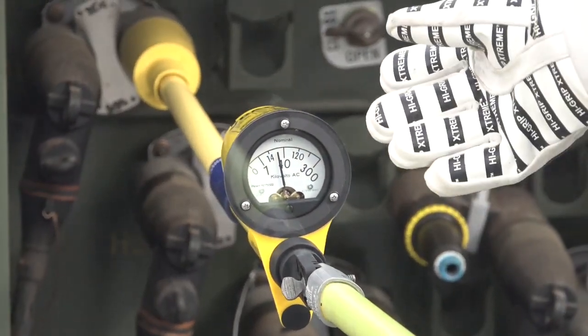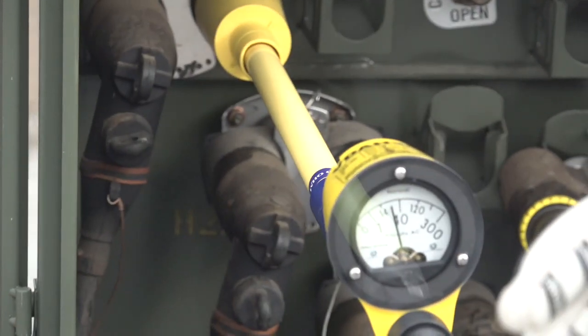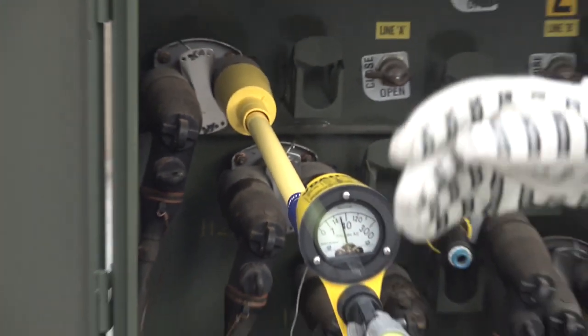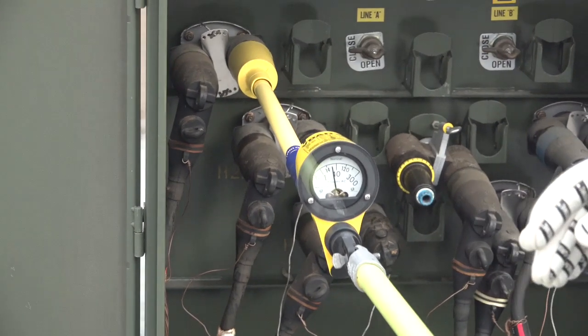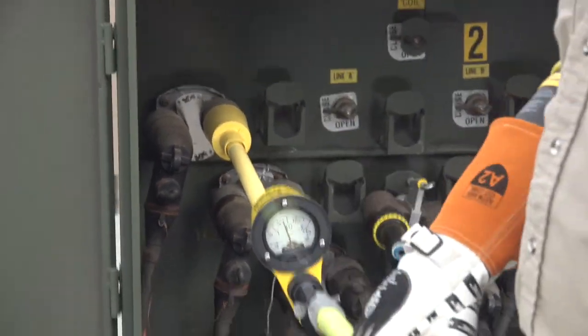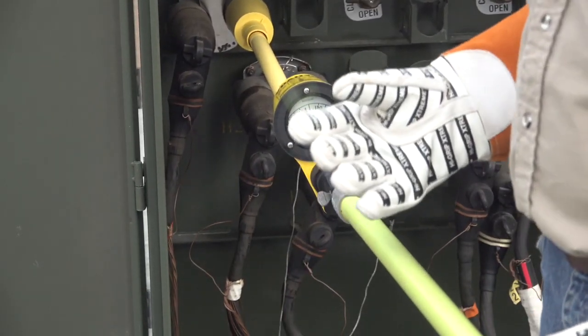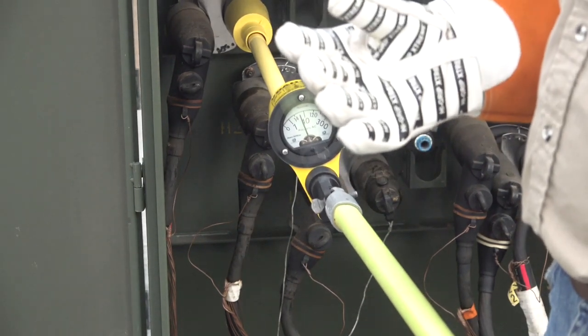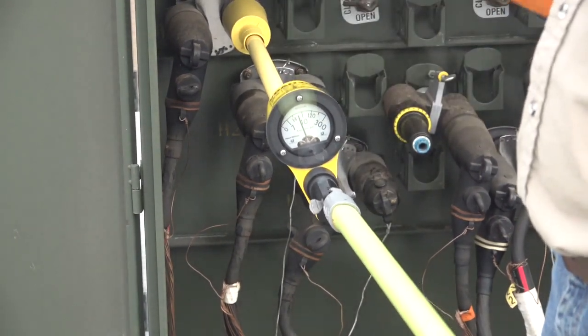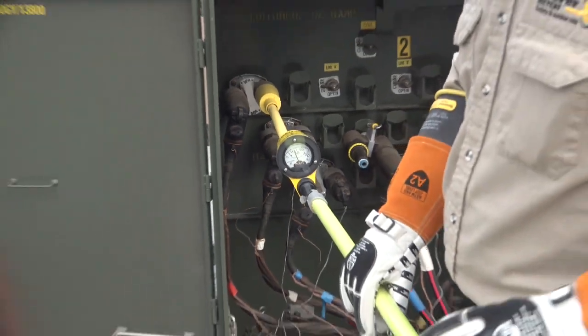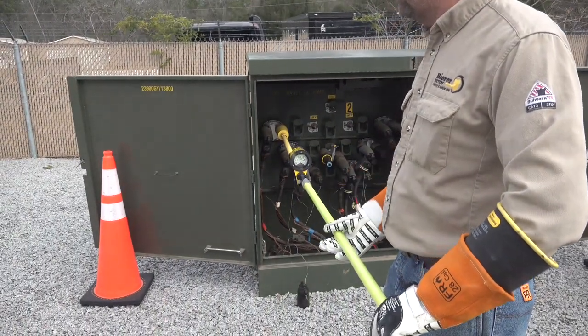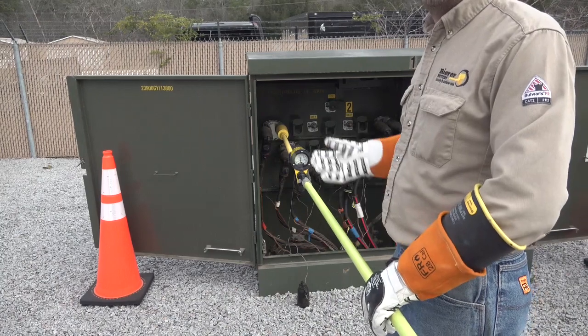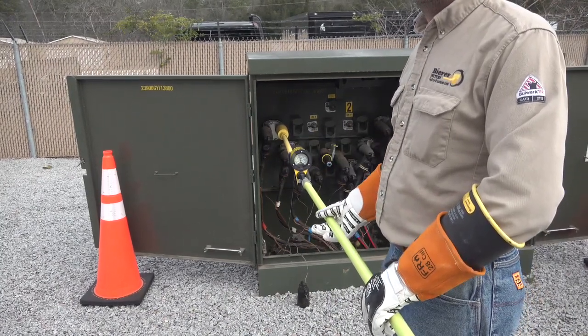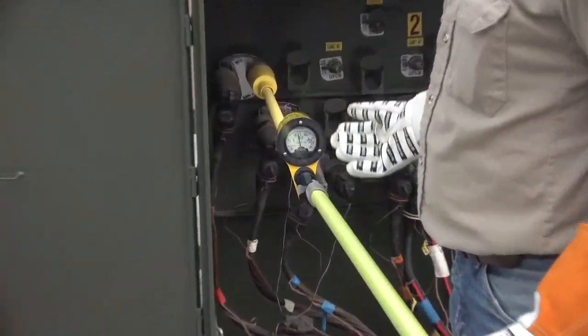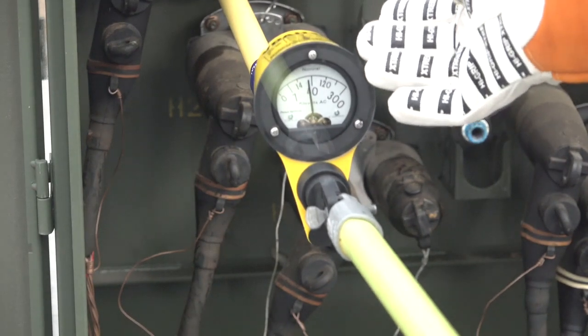And notice the reading is lower on the scale now. It's further away from the 40 kV. So it's again closer to the middle of the 14 and 40. And you'll notice if I actually move my hand closer to this scale, I can actually make that reading get higher. So again, not just getting the device away from the ground plane, you want to make sure your body is also far enough away from the tool so you don't start coupling with the tool and adversely affect the reading. So if I move my hand closer, you'll notice that reading will get higher and higher.